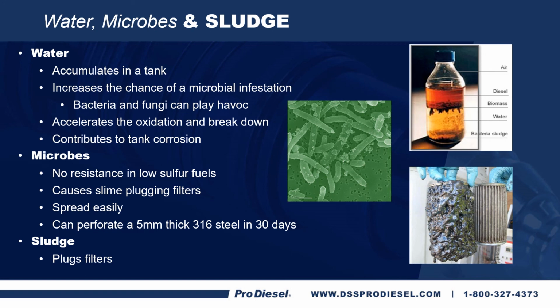Some of these microbes are so corrosive that they can eat through 5mm thick 316 steel in just 30 days. Because we went to low sulfur fuels, there's just no resistance in the fuel now because of that. It causes slime, it plugs up your filters, it spreads real easy from one piece of equipment to another. If you're using the same nozzle to fill them, you could even pick up contamination at a fuel service center. So be careful where you're getting your fuel. Make sure that you're putting the right additives and taking care of it, making sure this doesn't happen to you. And sludge, just as you can see there in the picture, just plugs up your filters. And of course, if any of that gets through, it clogs up an injector, and then you've got big trouble.